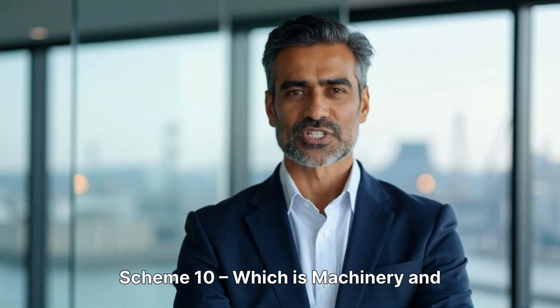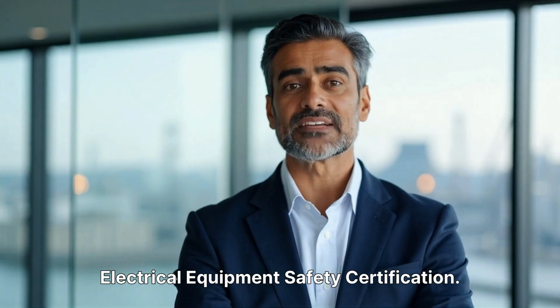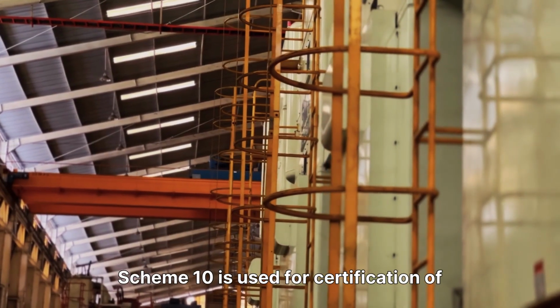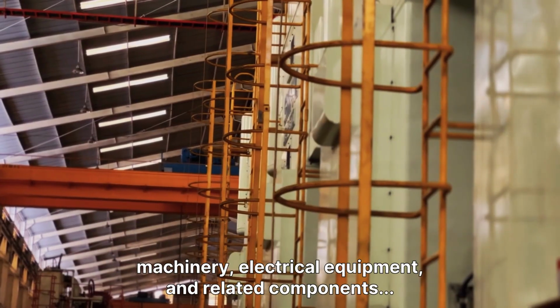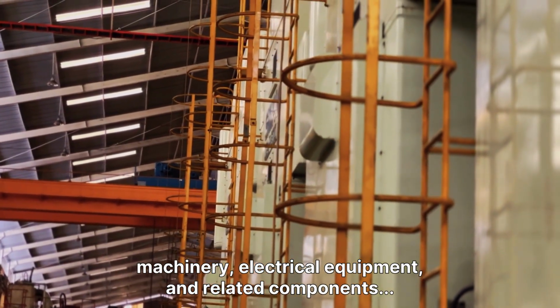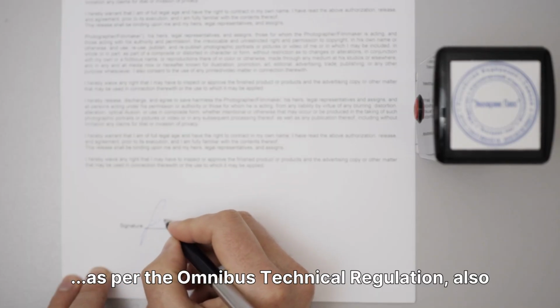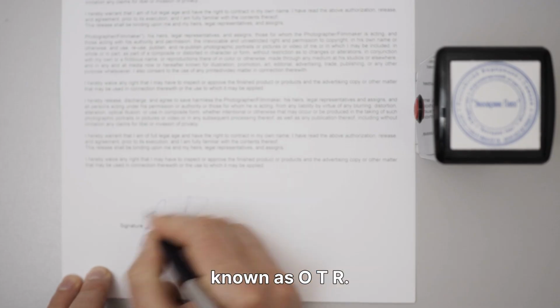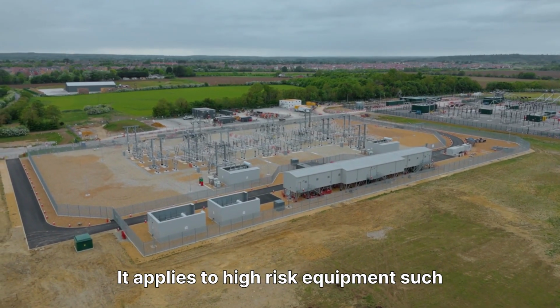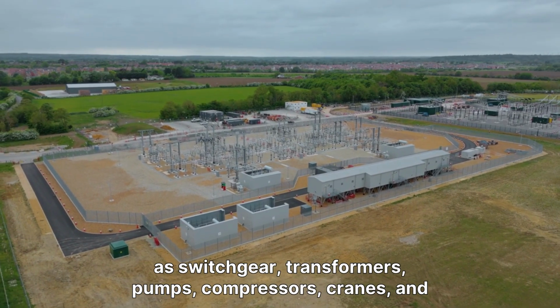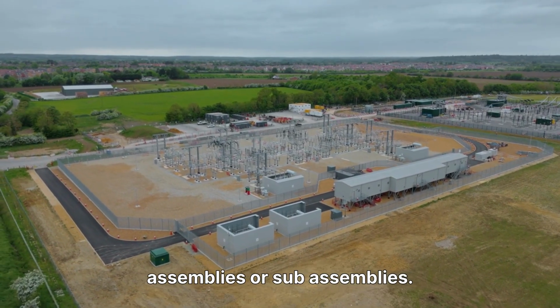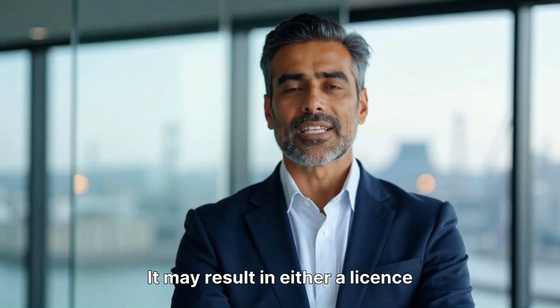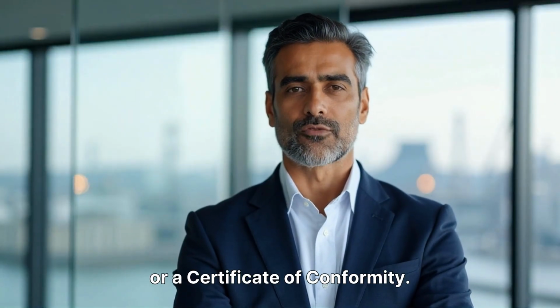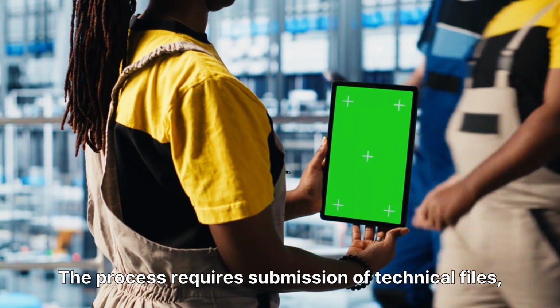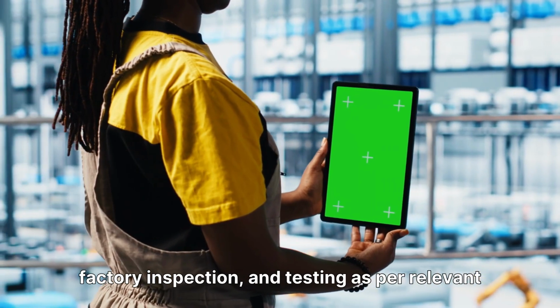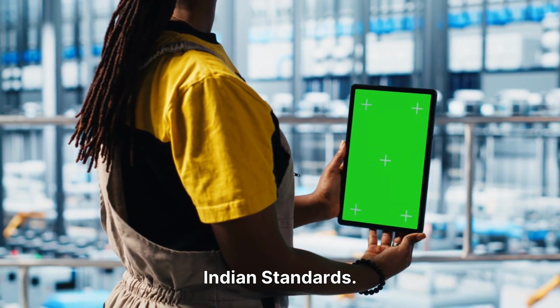Scheme 10, which is Machinery and Electrical Equipment Safety Certification. Scheme 10 is used for certification of machinery, electrical equipment, and related components, as per the Omnibus Technical Regulation, also known as OTR. It applies to high-risk equipment such as switchgear, transformers, pumps, compressors, cranes, and assemblies or sub-assemblies. It may result in either a license or a certificate of conformity. The process requires submission of technical files, factory inspection, and testing as per relevant Indian standards.